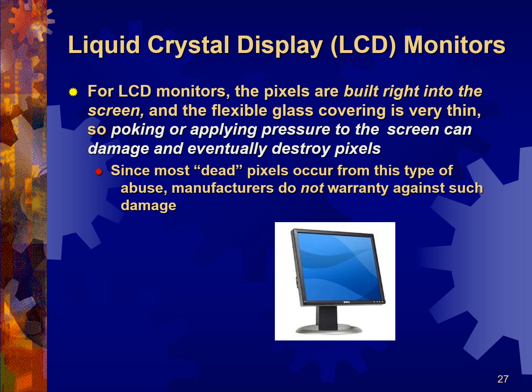And so that pixel or that region of pixels doesn't broadcast as it should, and it typically shows up as a spot that's dimmer on the monitor. We can't have that in medical imaging, so if there is a damaged monitor, it should be replaced.